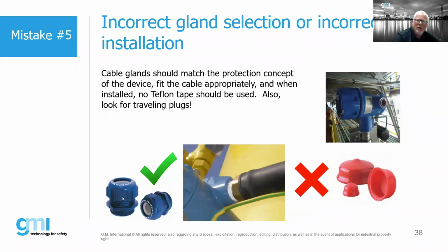We certainly can use blue cable glands, but it is, again, like the marking and the identification of cables, blue cable glands are not necessarily a requirement unless the client is specifically saying so. So we can use non-blue cable glands for running IS circuits, at least as far as the standard is concerned. So again, people can use them. There's no problem with doing that. Just make sure that they're certified for the application.